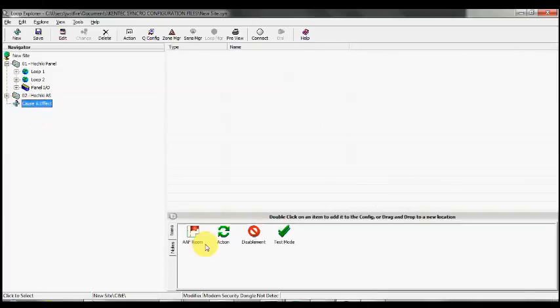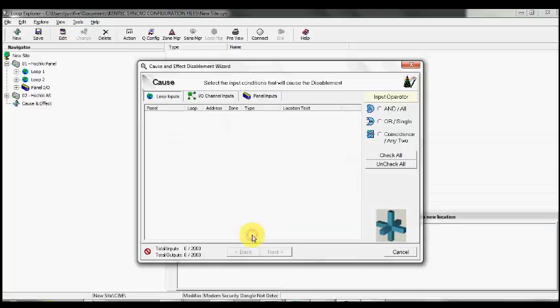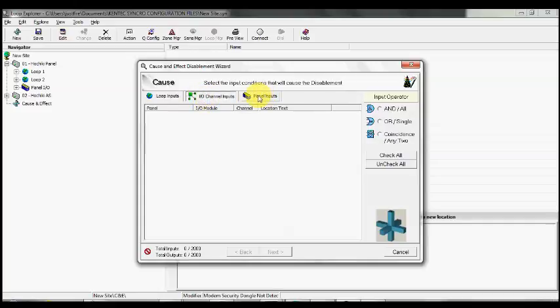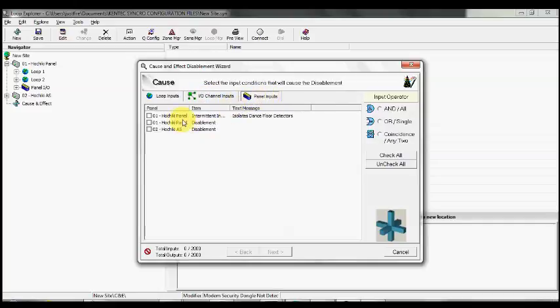Now we can start to create the cause and effect. I'll open up the Cause and Effects Wizard, select the Disablement option, and open up the wizard. It says select the input conditions that will cause the disablement. The inputs we're looking for are not on the loop, not on the channel IO comms cards, but on the panel itself.